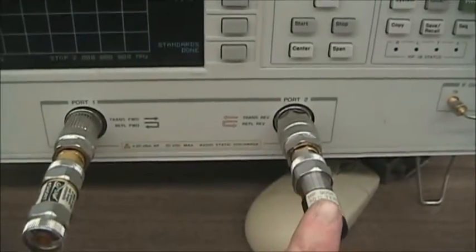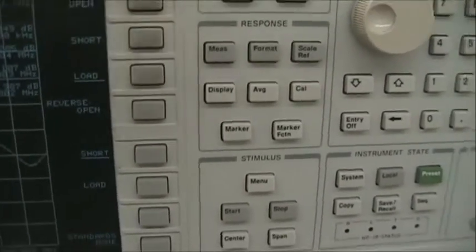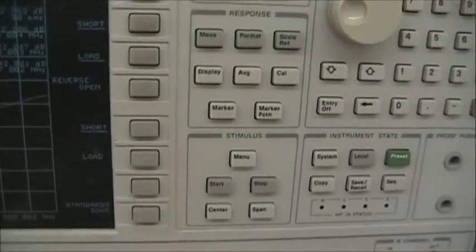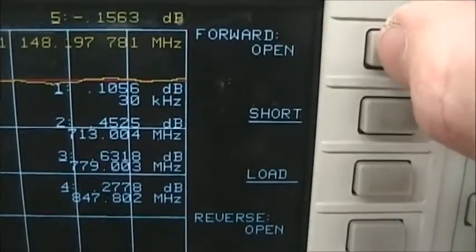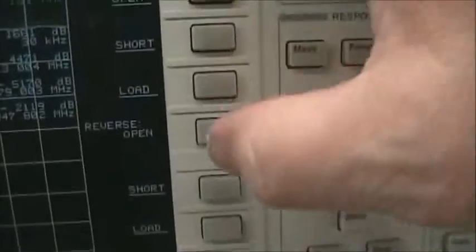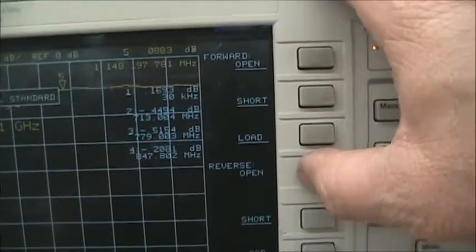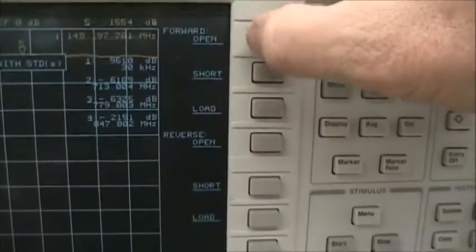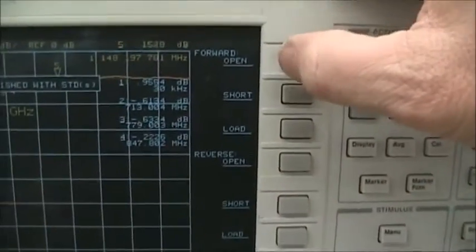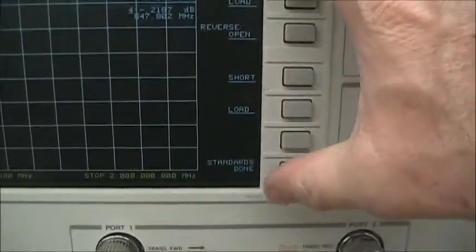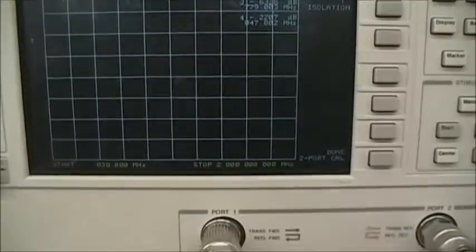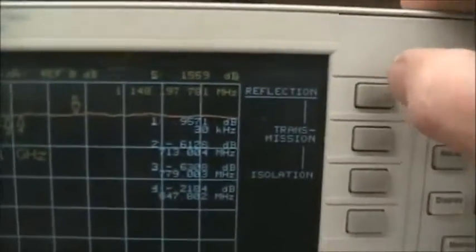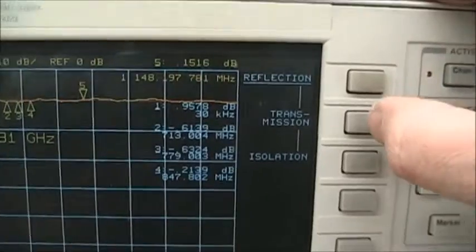Now the load is on port two, and the short is on port one. So, short for port one and load for port two. Open on port two. Now that the open, short, and load SOL have been done on both port one and port two, we can press the standards done. It's computing the coefficients, and the unit is ready to move on as we see the reflection is underlined. All of those standards are done.